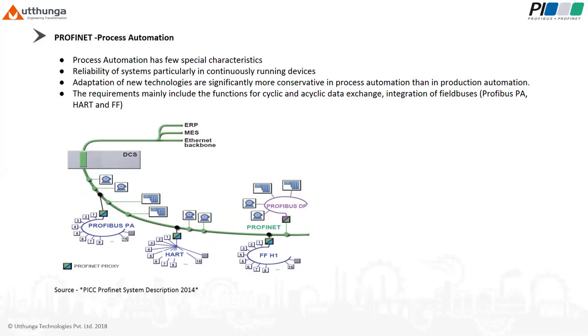The requirements mainly include acyclic data exchange and integration of fieldbuses like PA, HART, FF, DP, and also configuration in run, diagnostics, maintenance, redundancy. All these features should be added. You can see in the image itself, every other protocol is linked to a single PROFINET architecture, like PA, HART, FF H1, and DP are talking in a PROFINET architecture itself.